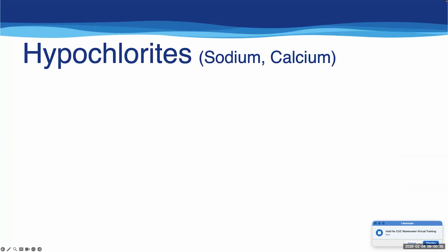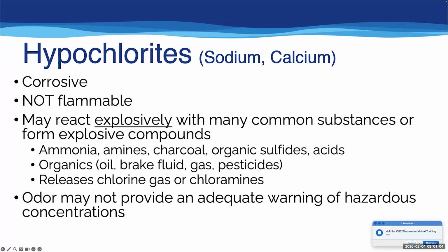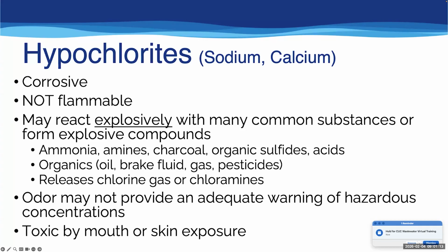Hypochlorites also have some safety issues that you want to be concerned about. So these are the liquid sodium hypochlorite and solid calcium hypochlorite. They're not really flammable in the sense that they won't burn when exposed to a match, but they can react explosively. They're corrosive. You don't want to keep them anywhere near compounds like ammonia and amines and organics, which is why, again, there are safety procedures and storage procedures. And the downside of hypochlorites is you may not smell hazardous concentrations like you would with chlorine gas. And they are toxic by skin or mouth. So again, PPE is critical.